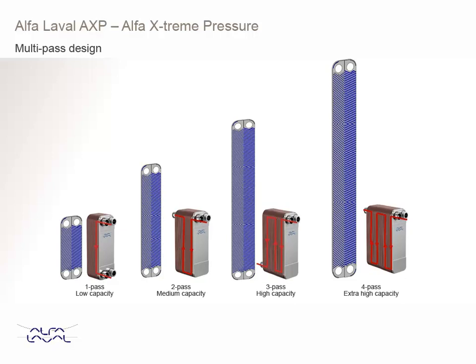Alfa Laval AXP can be designed with multipass. Multipass design has several advantages. First, you can get a close temperature approach if needed. Second, you can increase pressure drop in case of low flow. Third, you can handle high capacity duties.